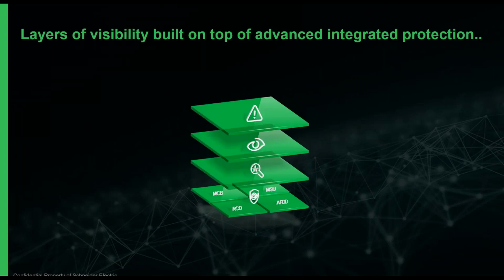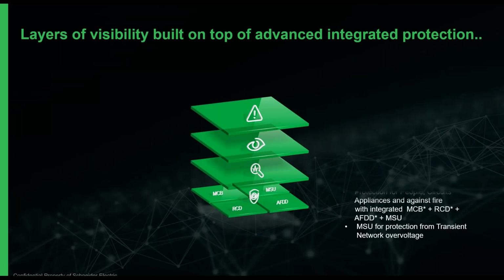So let's have a look in detail at what this system is. What does it consist of and what's inside? We get multiple layers of visibility built on top of the advanced integrated protection. The base layer is advanced protection. We've got what we're really familiar with in terms of miniature circuit breaker technology, RCD technology, an MSU, which is an overvoltage release or protection from network overvoltages, and also arc fault detection in this base layer of protection. We're familiar with most of these technologies in the UK.